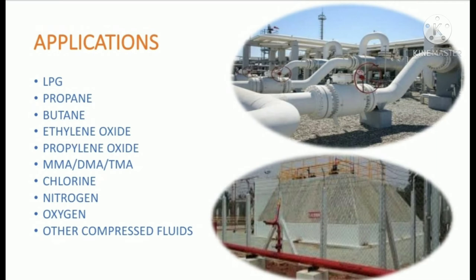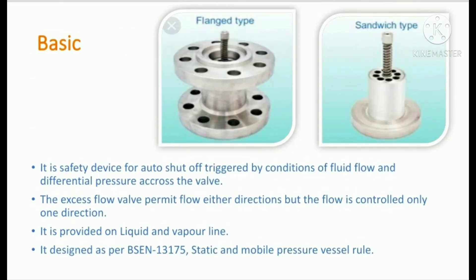It is available as a flanged end type, sandwich type, and screwed type. It is a safety device for automatic shutoff, triggered by the conditions of fluid flow and differential pressure across the valve. The excess flow valve permits flow in either direction, but flow is controlled in only one direction. It is provided on liquid as well as vapor lines, and is designed as per BS EN 13175 and static and mobile pressure rules.